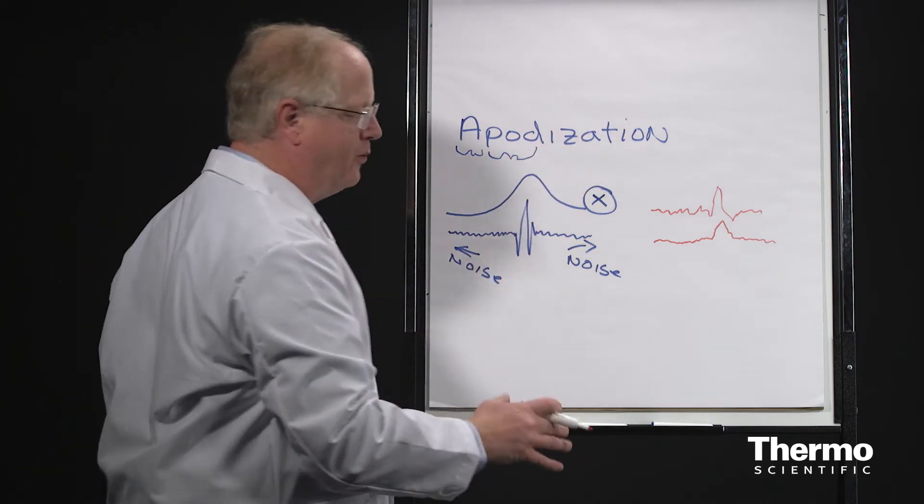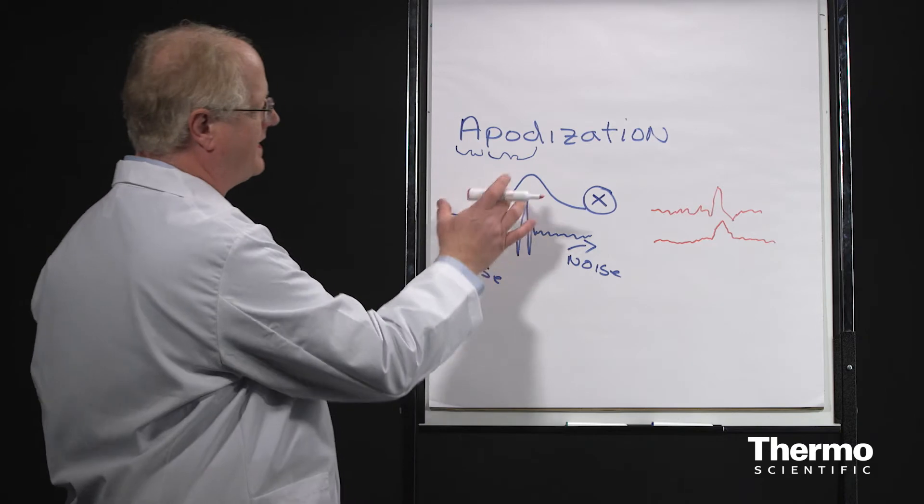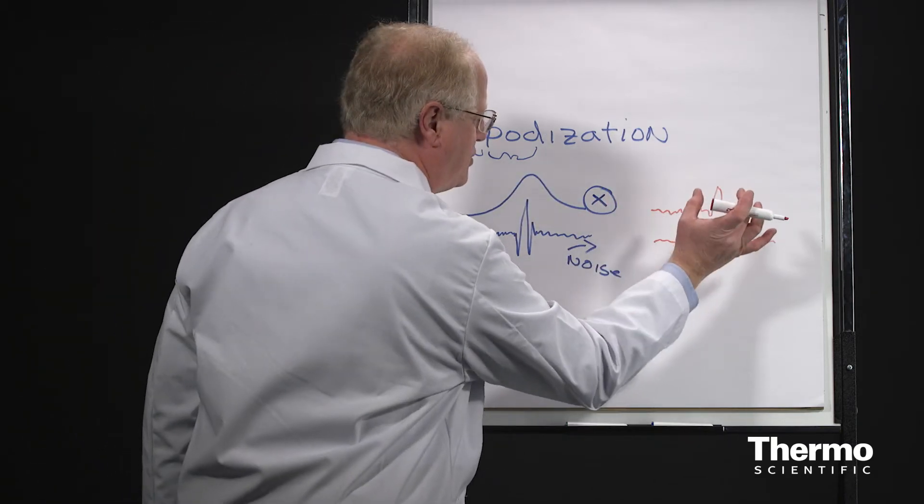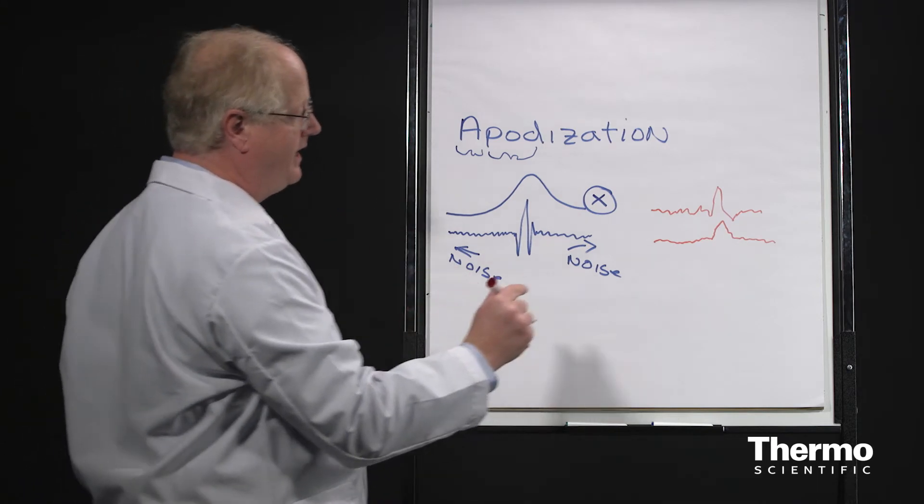Now it sounds like in that case you want to apply apodization. The problem is that if you apply a heavy apodization function, you also damage your signal. And I'm going to show you that when we stand at the instrument.